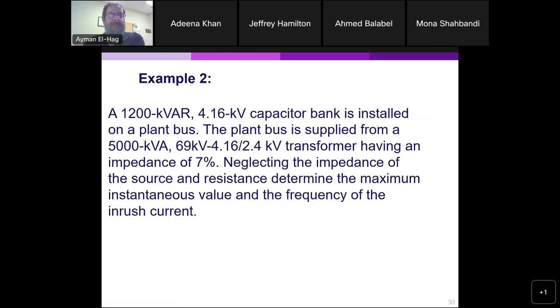Okay, so let's see this example here. We have a 1200 kVAR, this is your QC, 4.16 kV. This is the line to line voltage of your capacitor installed on a plant bus. The plant bus is supplied from a 5 MVA or 5000 kVA, 69 by 4.16 to 2.4 kV transformer. This is the line to line and this is the phase voltage. So this is a step down transformer. The capacitor is connected at the secondary of the transformer at the line to line voltage level, the transformer having an impedance of 7%.